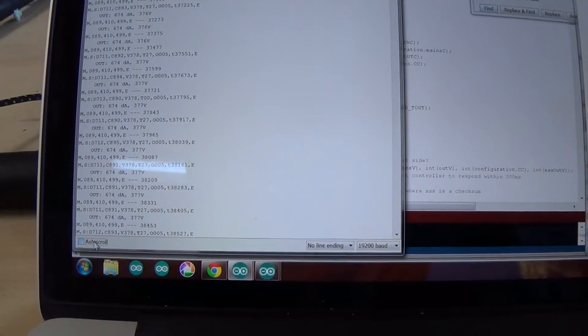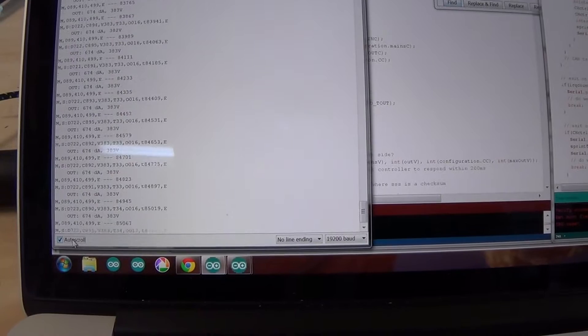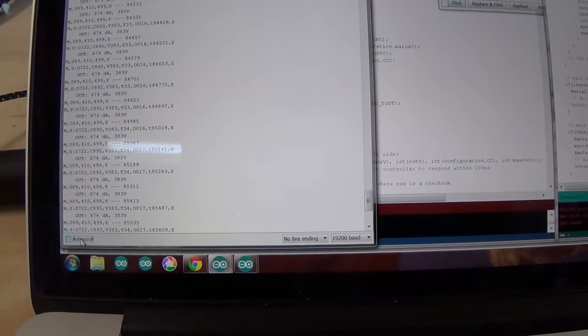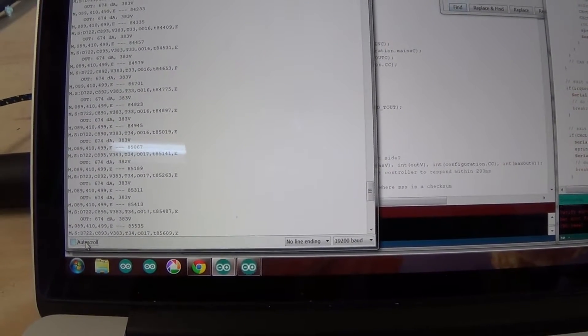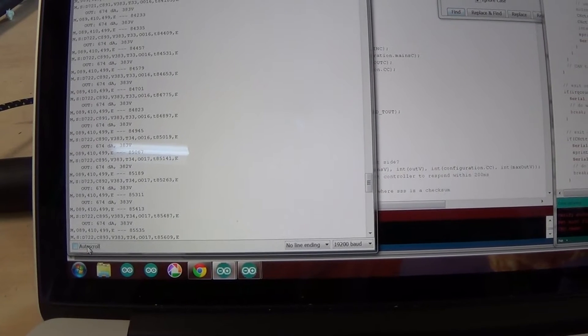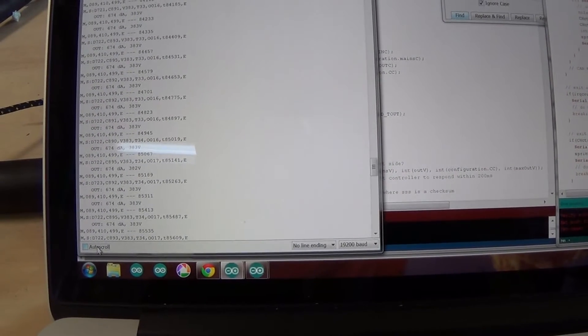And on the screen, about 90 A. Let's see what the temperature is right now. 34 centigrade, heat sink temperature after about 2 Ah into the battery, 383 volts.